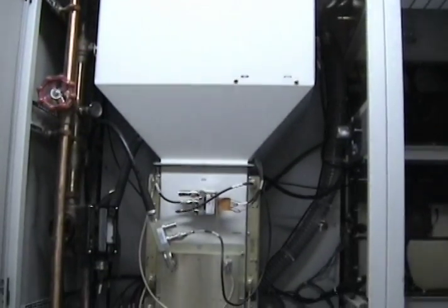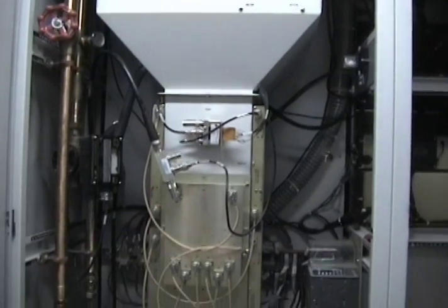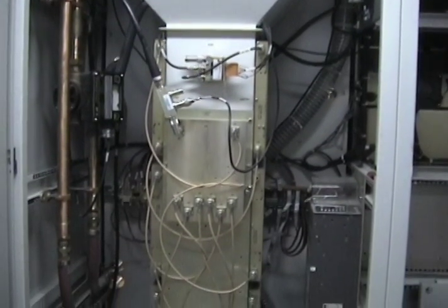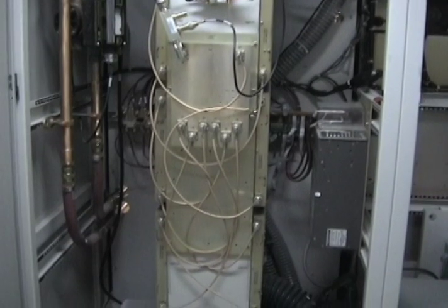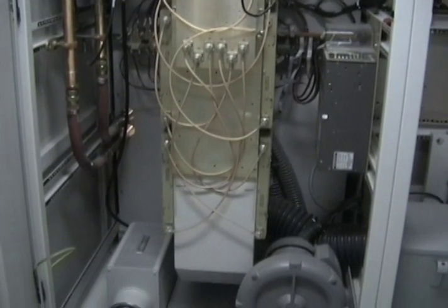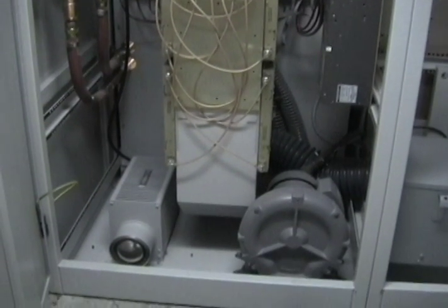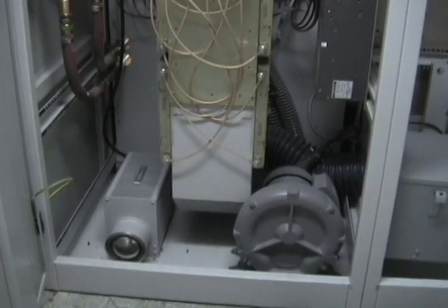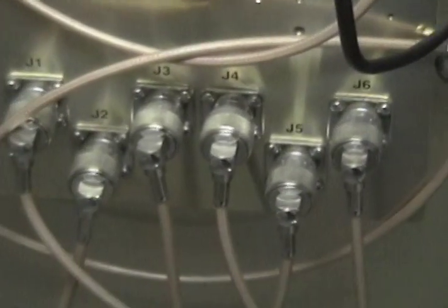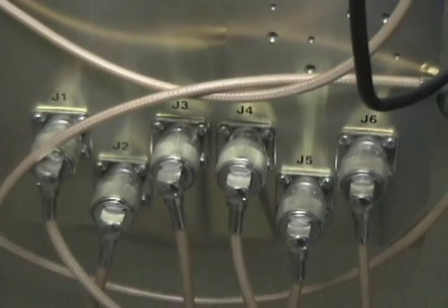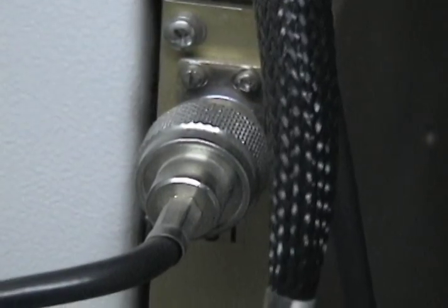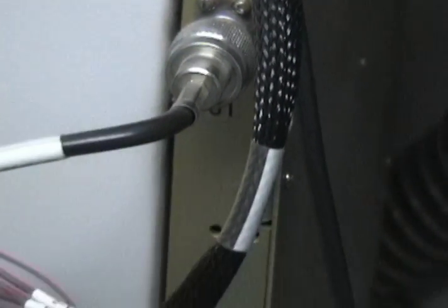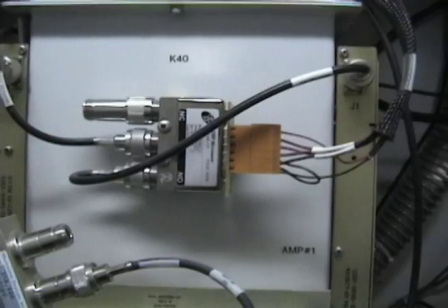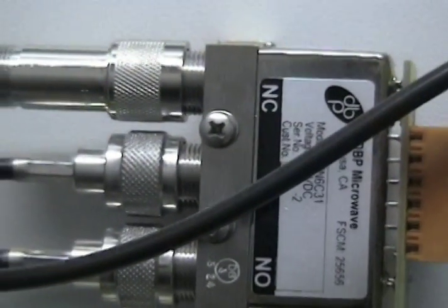At the rear of the IOT cabinet are the IPAs, or intermediate power amplifiers, which are used to amplify the signal from the exciter to a level required by the IOT. Several solid-state amplifiers are needed, and the outputs are combined here and monitored with a directional coupler. An RF switch is used to make sure that all RF is off going to the IPAs when maintenance is performed.